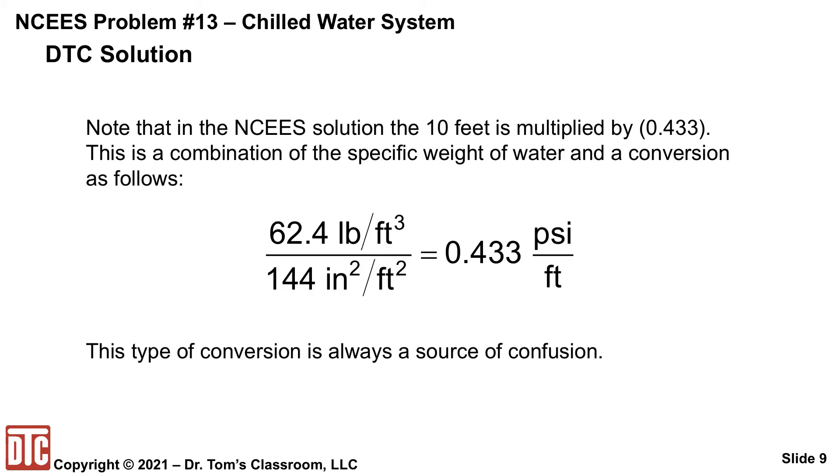Now, there was a term here of 0.433 and you kind of wonder where it was. They took 10 feet and multiplied by it. Well, what it was was the conversion that we just did. The gamma 62.4 divided by the 144 inches squared per foot squared. So you got this 0.433. They didn't give it as any units. It just said 0.433 and a lot of confusion as to what is that.